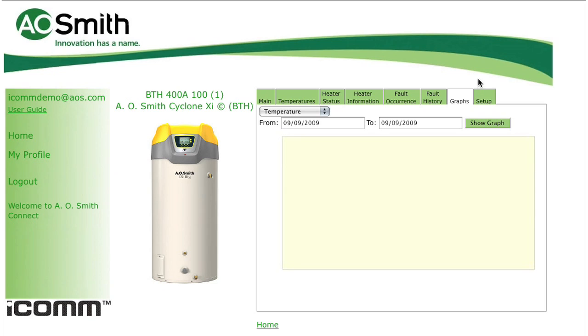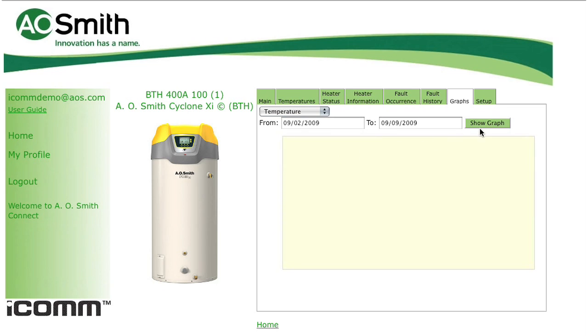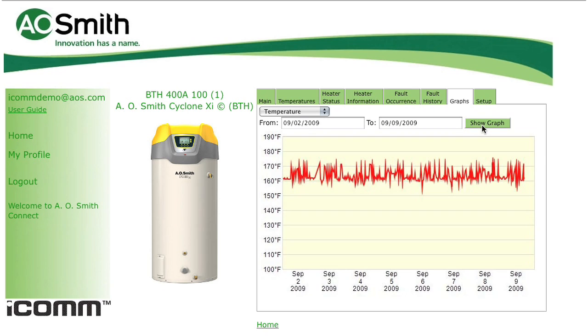The graphs tab contains some of the most useful data available within iCOMM. A pull-down menu gives you options to graph four different sets of information. Selecting temperature and then a seven-day period on the calendar results in a graph showing outlet temperatures for those exact days. This can be as short as a one-day view or as long as a 90-day one. This is an excellent way to show if your water heater is sized properly and is able to maintain the desired temperature.